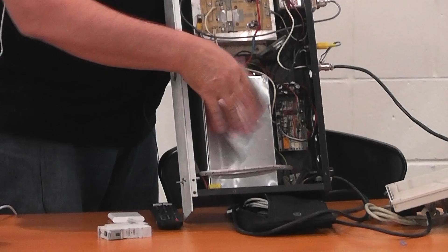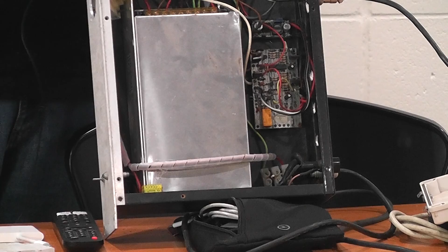I've attempted to keep the mains wiring neat. I didn't have room to sneak it around the side like I normally do, so I've covered the 240 volt cabling in spiral wrap, which effectively double insulates it. There's two layers of insulation, so if there's any rubbing it's going to go to the chassis, and as soon as any voltage appears in the chassis, the RCD should operate.